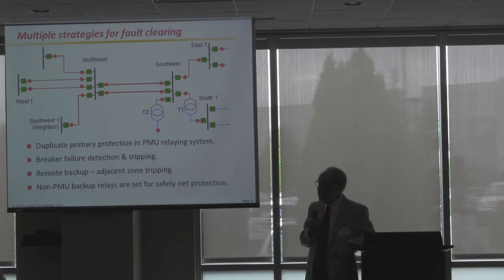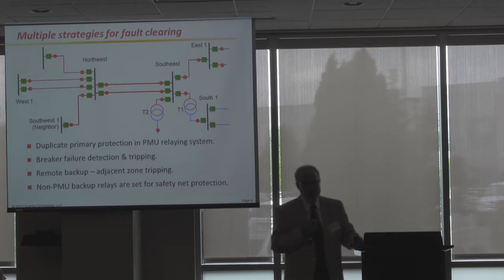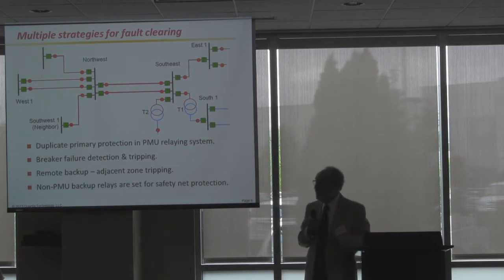When you actually look at how to do this, today is not a good time to start laying out detailed strategies for how this would get done. But there are a variety of nested sequence strategies for how we could use this differential current measurement to detect where a fault is, what's going on, and how to disconnect it. We can even duplicate the primary protection. It'll be a little slower than the current differential relays we have today, and issue an additional set of trips to the breakers that should clear a fault. We can do breaker failure detection by its effect as well as what's going on at the breaker, and do the backup tripping that would be done for that. We know what's going on with the data that we have.